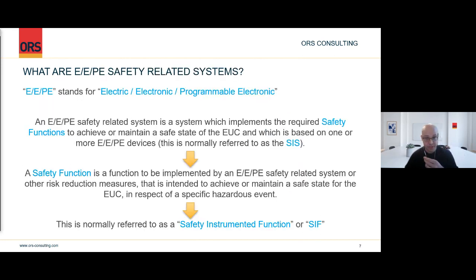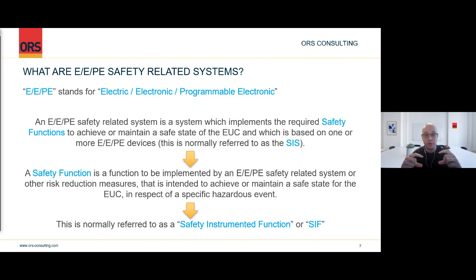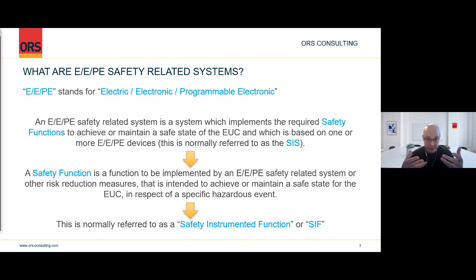E/E/PE safety-related systems are safety functions which achieve or maintain a safe state of the EUC and which are based on one or more E/E/PE devices. When several of these functions are implemented by one system, that's called the Safety Instrumented System, or SIS. Each of the functions within that safety instrumented system is called a safety function or a Safety Instrumented Function — a function implemented by an E/E/PE SIS intended to achieve or maintain a safe state for the EUC in respect to a specific hazardous event.